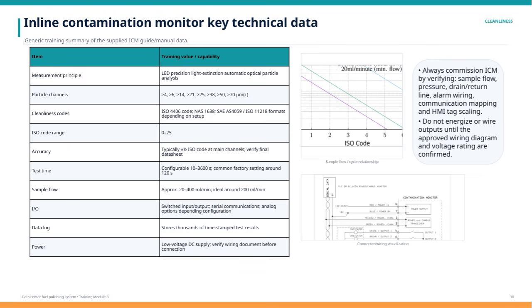Testing time is fully configurable, usually set around 120 seconds in typical factory settings, but it can be adjusted anywhere from 10 seconds to an hour based on the need. Sample flow rates are flexible as well, ideally maintained around 200 milliliters per minute, but can vary between 20 to 400 milliliters per minute. Regarding inputs and outputs, the ICM supports switched digital in and outputs, serial communication, and analog options, which depend on the particular configuration installed. It also has robust data storage capability, saving thousands of time-stamped results to track contamination trends over time. Power supply for the unit is low-voltage DC, so it's critical to verify wiring documents thoroughly before making any connections to ensure safety and proper operation.